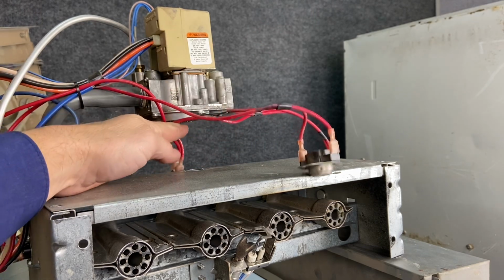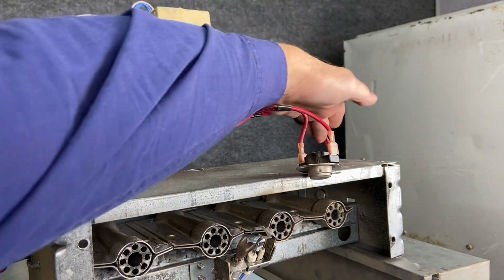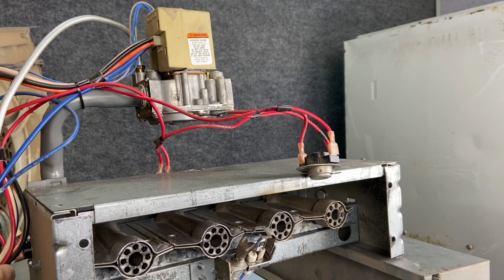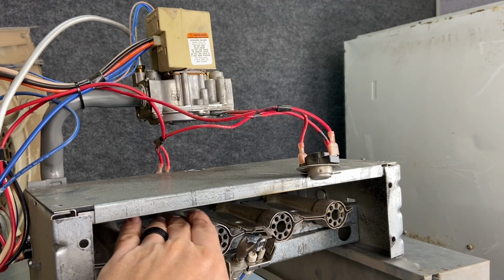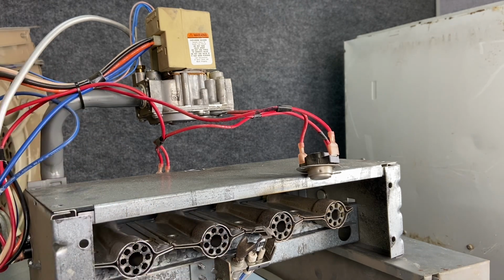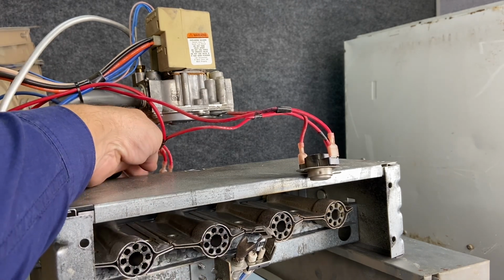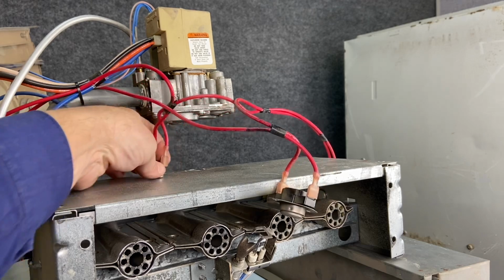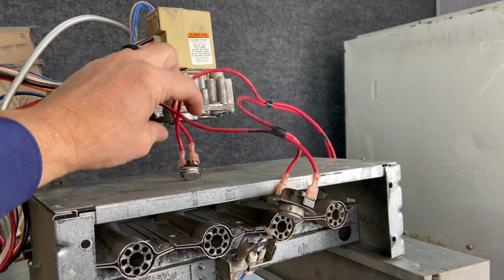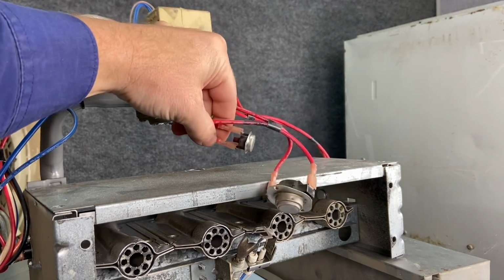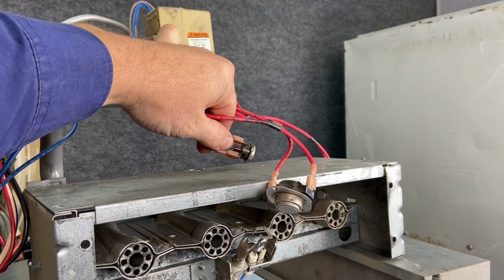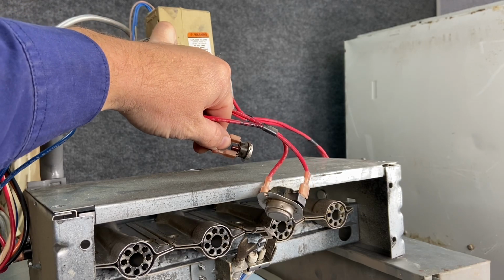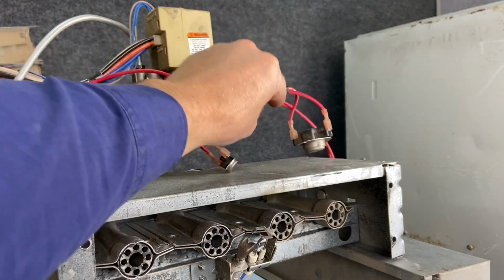Here we have our flame rollout, another flame rollout, and these 2 wires here, they go to a flame rollout on this side here. So if the flame was to roll out of the heat exchanger back this direction, those limits would shut off. Remember again, those limits are manual reset. So if we see on the side, there's a little button right there, and you can press that button to reset it. Now never just press that button, find out why, what's going on with it.